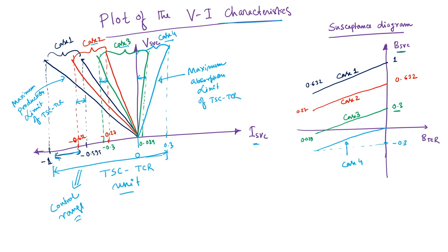Now, one should understand that this is the entire control range of this TSC-TCR. It can produce VAR up to 1 per unit, and it can absorb VAR up to 0.3 per unit. So it can also have a non-zero production and non-zero absorption because of this TCR operation.